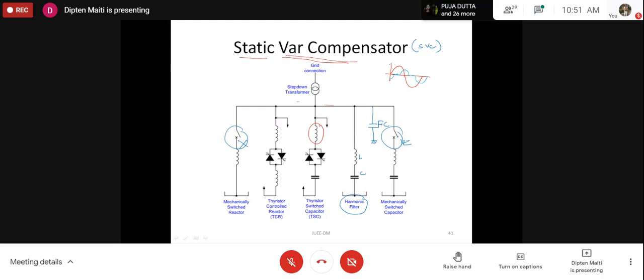So as if we can say from the opposite view, that the inductance value actually changes if you look from the fundamental point of view. So we have the same inductance connected. However, using a combination of SCRs, we can delay the firing angle such that it is as if the inductance value has changed, and so due to the changed value of the inductance, current drawn from the source has reduced or increased, or current drawn from the inductance should change.